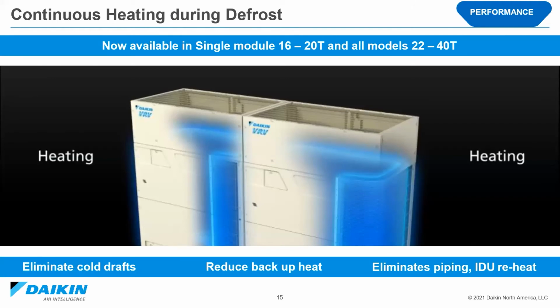An important benefit with the Emerion is the ability to have continuous heating during defrost for all units 16 tons and above. As the 16 to 20 ton module now has dual circuits, they can literally defrost one side of the unit while the other half can run in heating. During cold winter nights, it's a great benefit to be able to continue to heat the space without disruption.